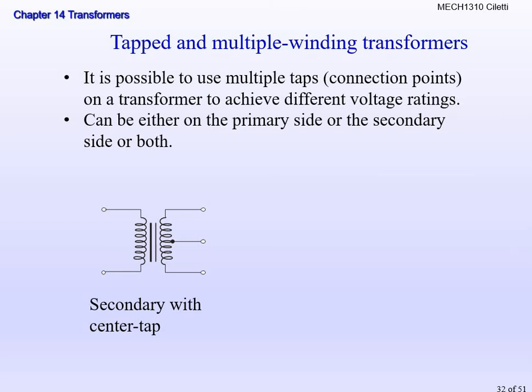Your dryer requires 240 volts, but you're using two 120 legs of AC to create that 240. So it's split phase, not two phase — two phase doesn't exist. We only have single phase and three phase.